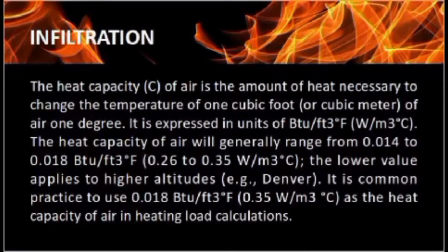The heat capacity is expressed in unit of British thermal unit per cubic foot, degree Fahrenheit, or watt per cubic meter, degree Celsius. The capacity of air will generally range from 0.014 to 0.018 BTU per cubic foot, degree Fahrenheit, and 0.26 to 0.35 watt per cubic meter, degree Celsius. So the lower value applies to higher altitude. Example, Denver. So it is common practice to use 0.018 British thermal unit per cubic foot, degrees Fahrenheit, and 0.35 watt per cubic meter, degree Celsius as the heat capacity of air in heating load calculation.